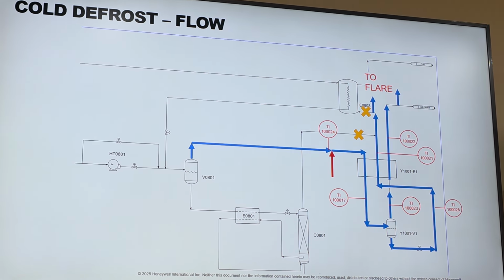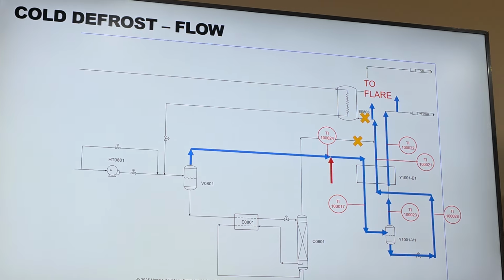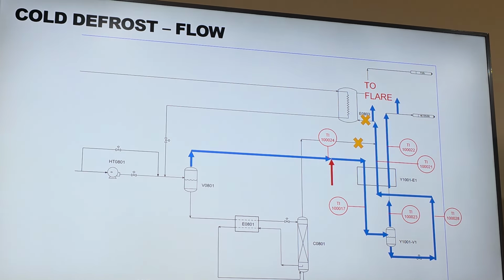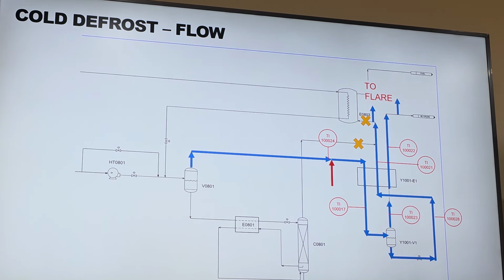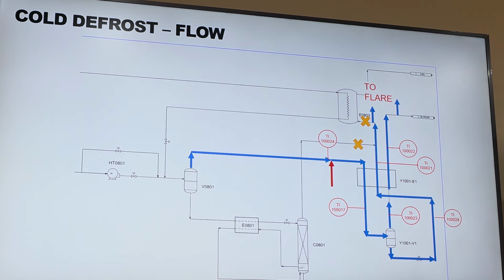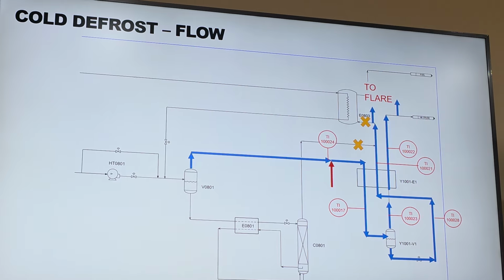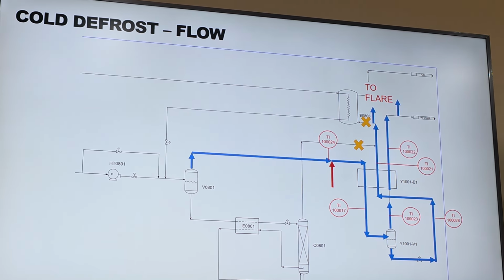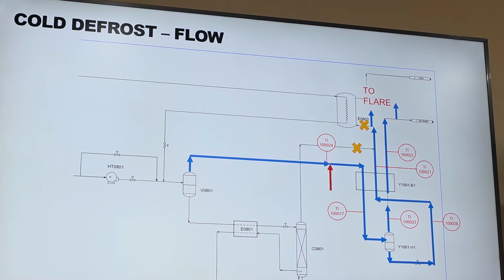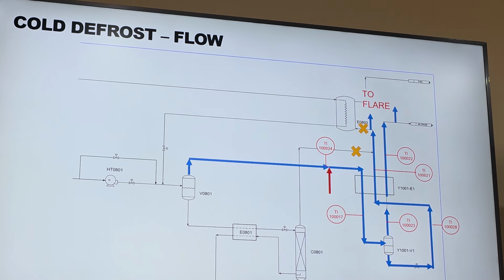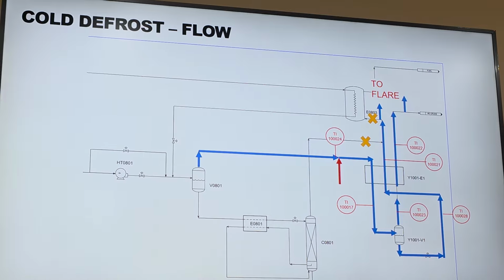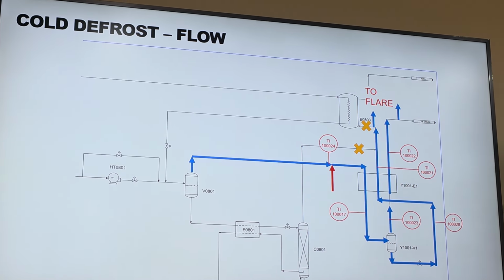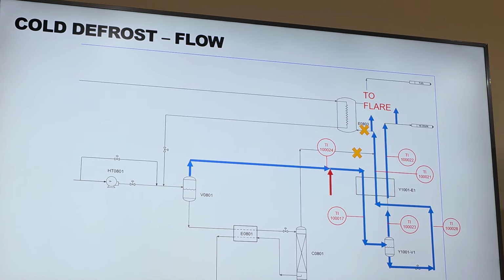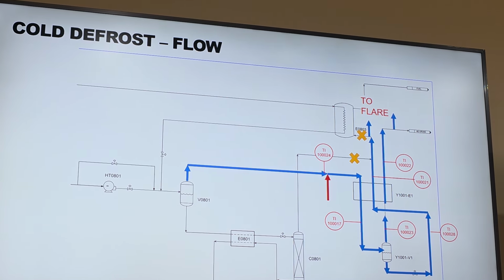But yeah, to answer your question, the only thing you can hope for is, because you have high pressure feed gas at some of your blend stations, you have high pressure feed gas that you step down across a JT valve, and that should be able to provide fairly cold defrost gas at your blend station. Yeah, if really needed. Which I don't know how cold that defrost gas can get when you step it down across the JT. Normally it remains, because it's coming from, we take it from unit 4, right? Yeah. It's compressor. Defrost gas.